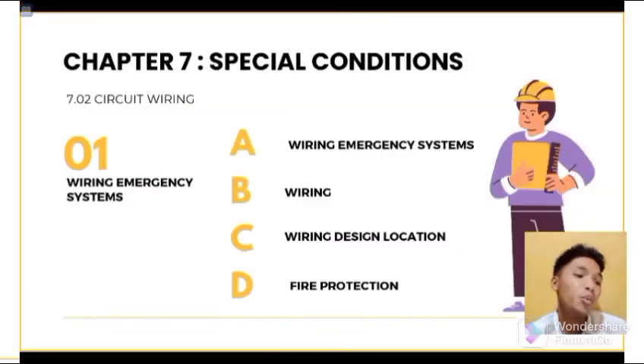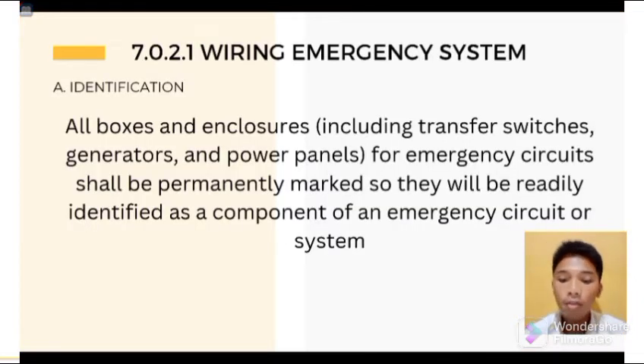Okay, so let's now move on with the 7.0.2 circuit wiring. First will be the wiring of emergency systems. First will be the identification. All boxes and enclosures, including transfer switches, generators, and power panels for emergency circuits shall be permanently marked so they will be readily identified as a component of an emergency circuit system. Letter B, wiring. Wiring of two or more emergency circuits supplied from the same source shall be permitted in the same raceway, cable, box, or cabinet.